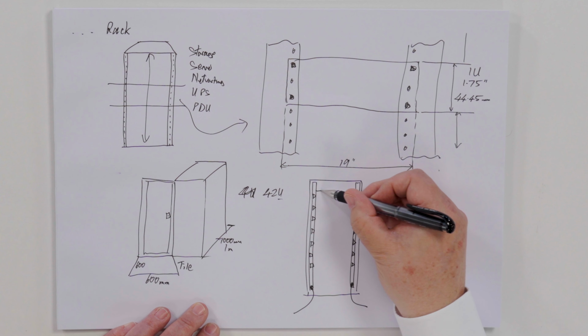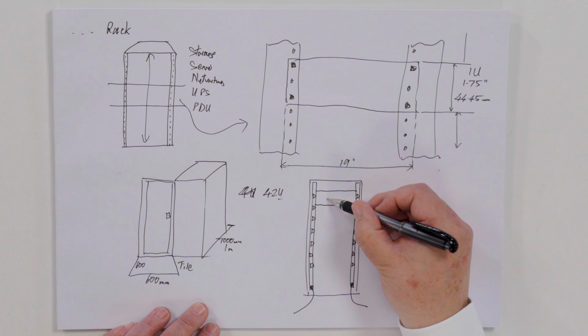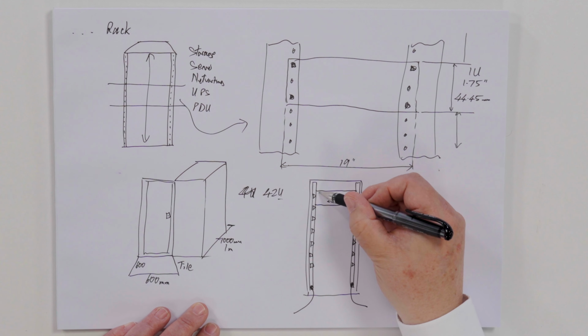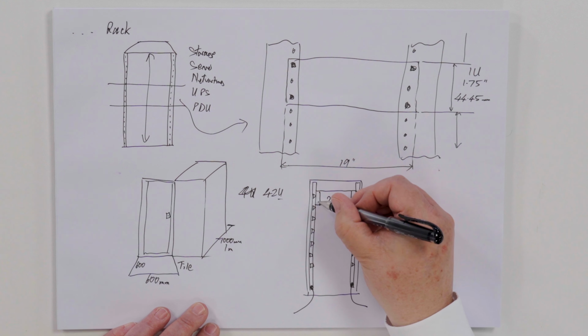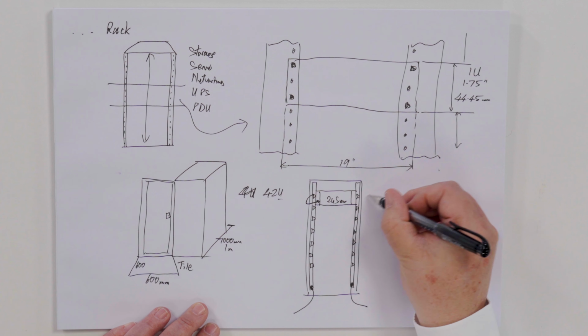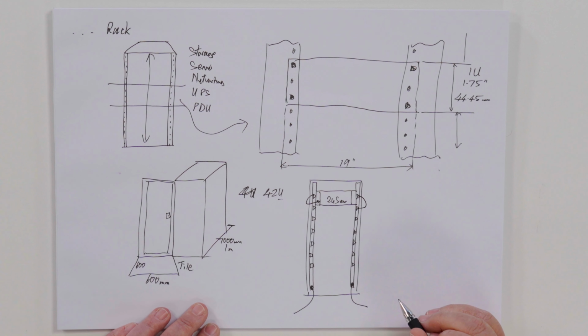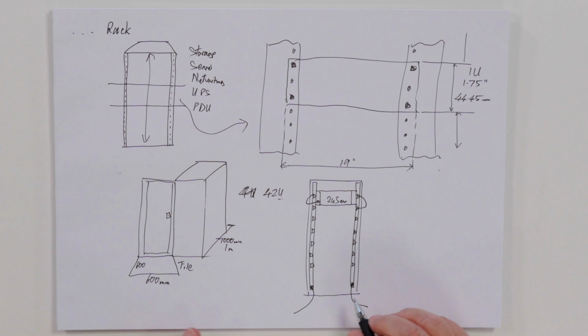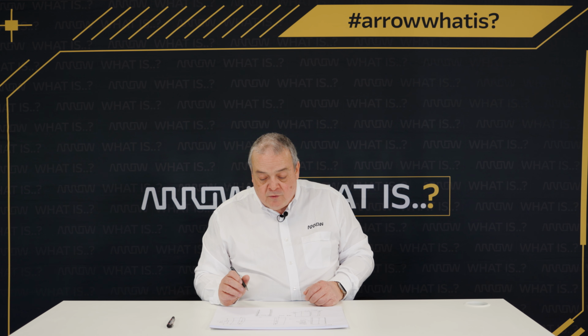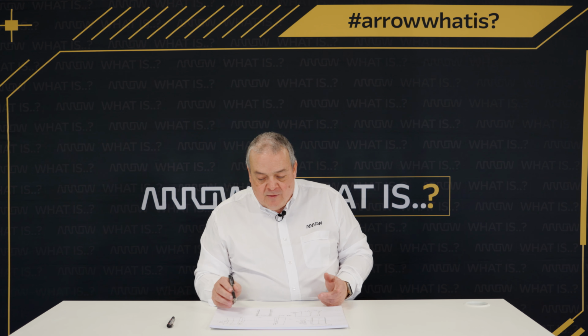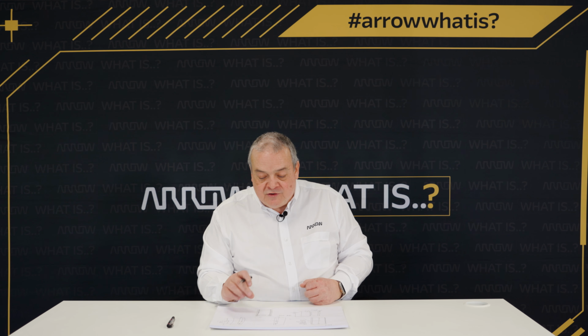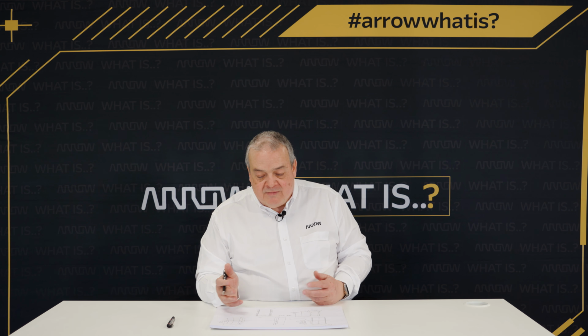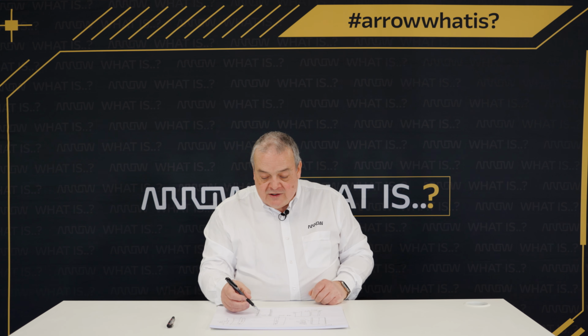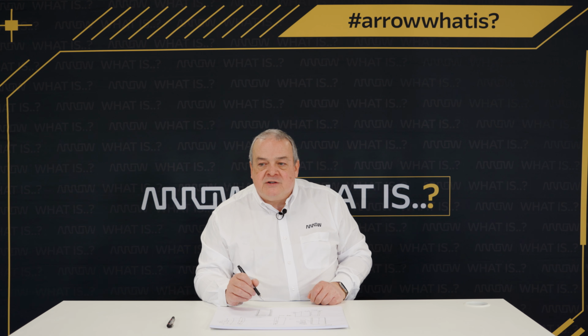Now, if we dropped a device into our rack - a nice 2U server - this will have a power supply on the left and a power supply on the right, and we can connect these power supplies to the sockets already provided by the power distribution units in the back of the rack. This makes it very straightforward to provide short power cables. We're not having cables trailing all over the floor making a mess. Keeping cables short makes it neat and tidy, easier to cable, and easier to see what you're doing around the back of the rack, with lots of space for other products and devices.